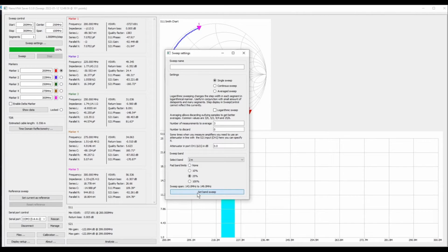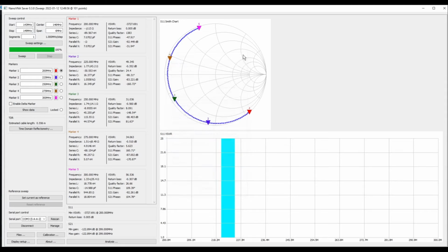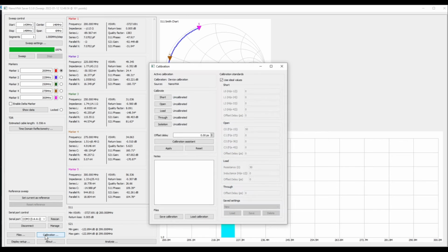I'm going to click this button, Set Band Sweep, close the dialog box, and then up under Sweep Control, I can see my settings have taken effect. The next thing I want to do is make sure that my NanoVNA is calibrated. So down here at the bottom under Serial Port Control, there is an option for calibration. I'm going to click that. Here you can see the device is not calibrated.